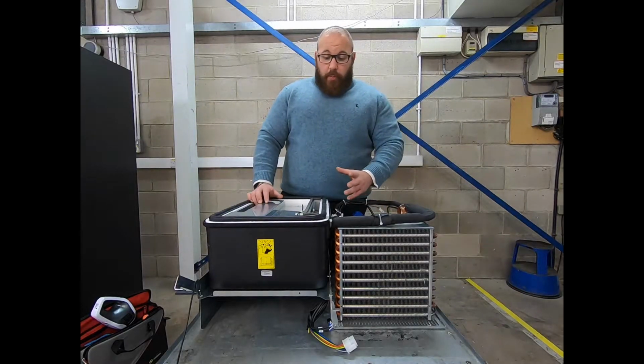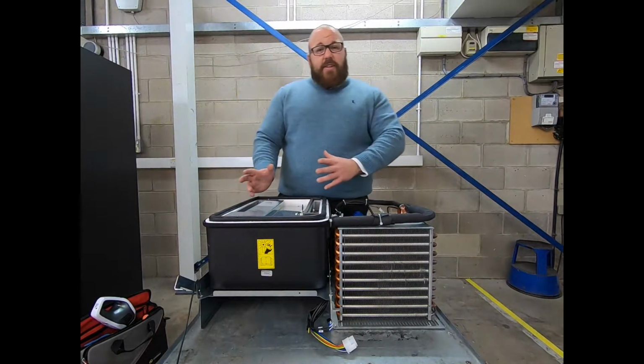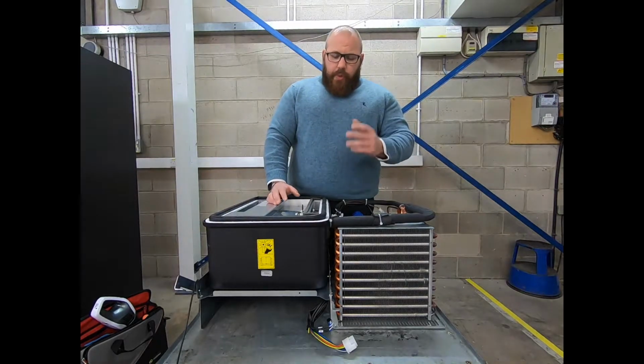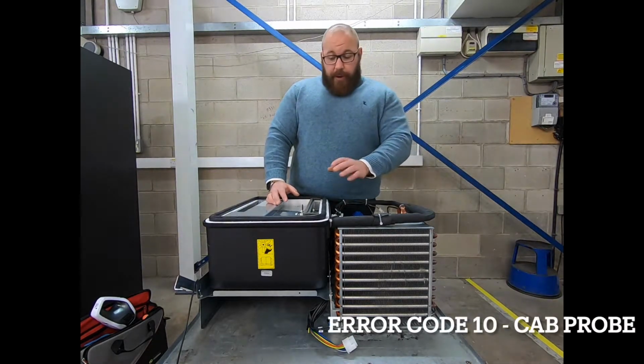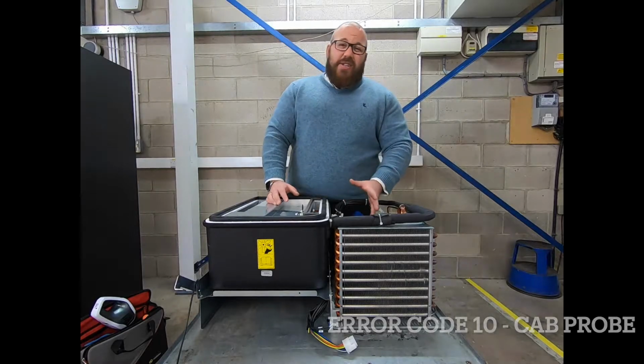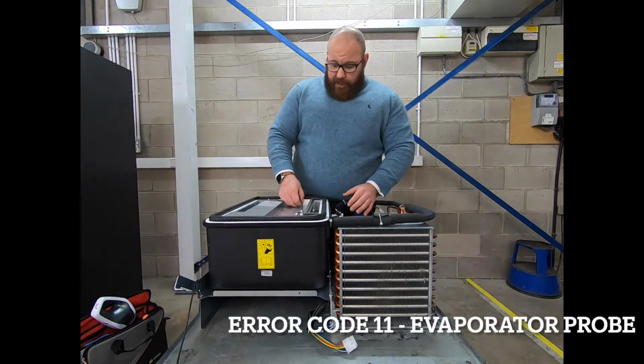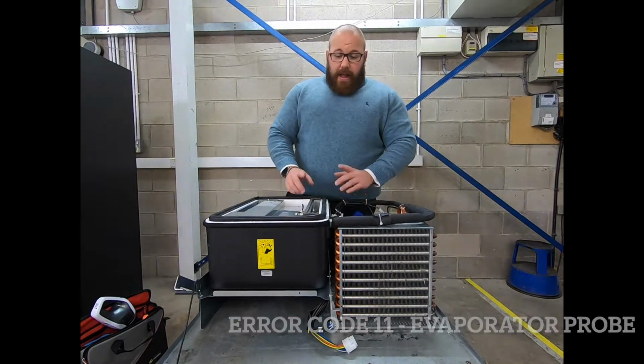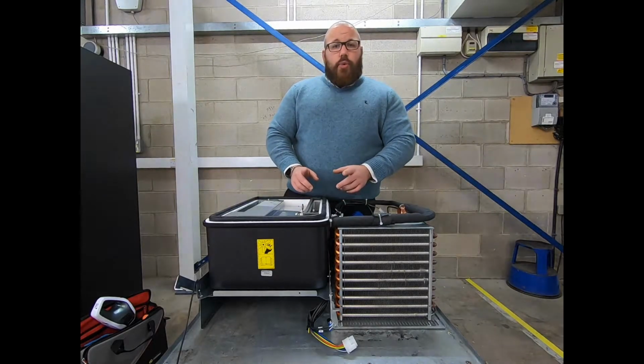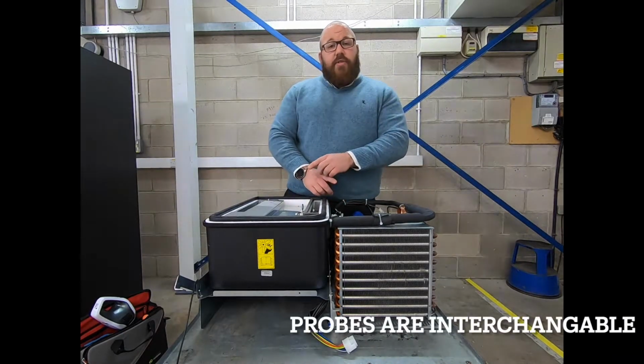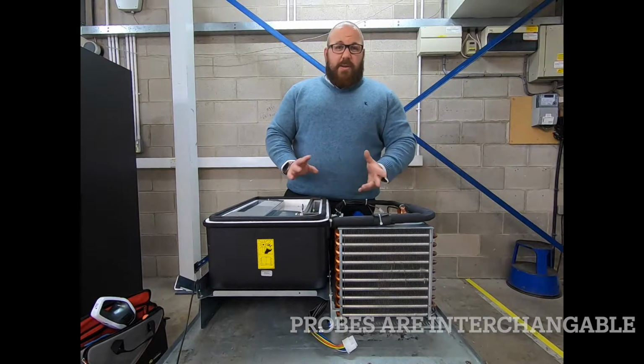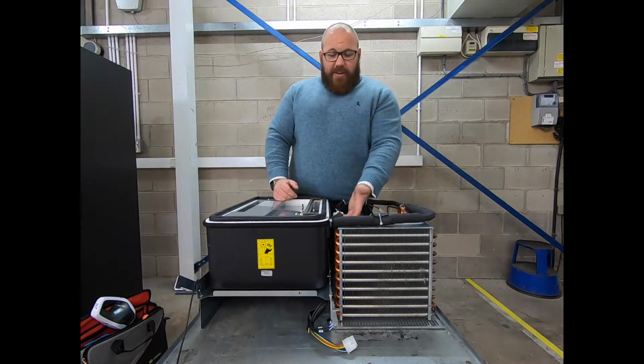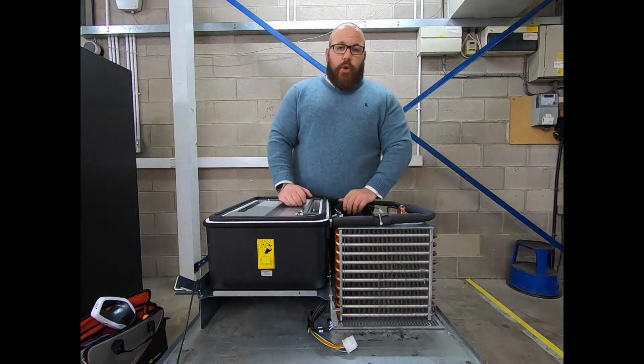Relating back to the 6000, if you had error code 10, I'd be looking at the cab probe, and if you had error code 11, I'd be looking at the evaporator probe. These are the same probe, so you can swap them to see if the error moves, if that's something you want to do for diagnostics. However, testing them will tell you whether they're working or not.